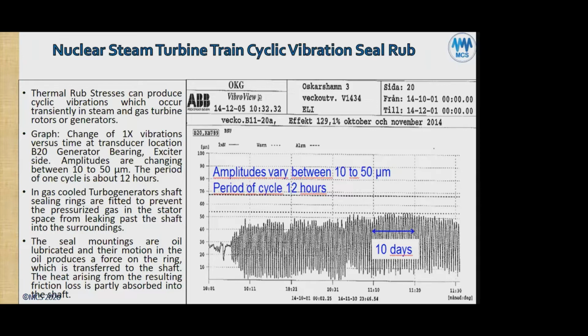So why would it have a period of 12 hours? Okay, we'll go back to this. So we'll read what's on the left hand, the comments from the person who had this problem. So thermal rub stress, well, I've added this. Thermal rub stresses can produce cyclic vibrations which occur transiently in steam and gas turbine rotors or generators. Now, from the author of that paper, he mentioned there's a change of the 1x vibrations versus time at transducer location B20 on the generator, on the exciter side. The amplitudes are changing between 10 to 50 microns.